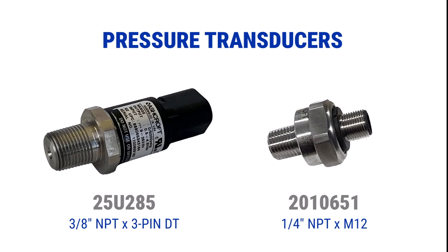Pressure transducers are analog sensors. Instead of simply opening or closing at a mechanical setting, transducers report the actual pressure of the system to the pump. They do this by varying the voltage level within the circuit connected to the P input. To be able to do so, the connection requires at least 3 wires. The G3 Max uses this varying voltage level to determine the status of the injector system. To do so correctly, it requires that more information be entered in the programming during setup.